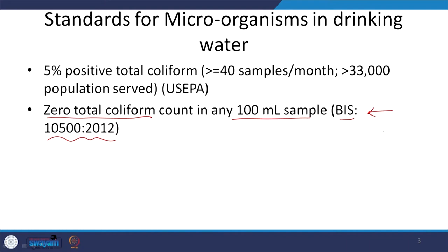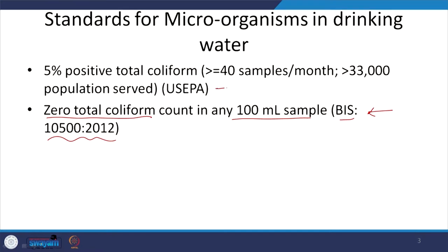Keep in mind that in India, regular testing infrastructure is still lacking, though improving. Comparing with US EPA: it allows 5% positive total coliform, but the rider is that you must take more than 40 samples per month, especially when the population is greater than 33,000. So the number of samples and acceptable positive rate are both specified — that is something to keep in mind.